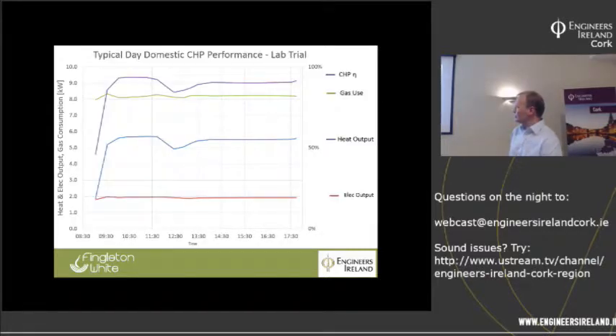Here are some test results from a typical day of our system in Dublin heating our office. On the left-hand side of this chart, you can see the electrical output, gas, and heat output, in kilowatts. This system is designed around a 2 kilowatt generator and a 5.5 kilowatt heat load. And what you're looking at is a gas consumption of 8 kilowatts, the green line, and that gives you an overall system efficiency of about 90%.